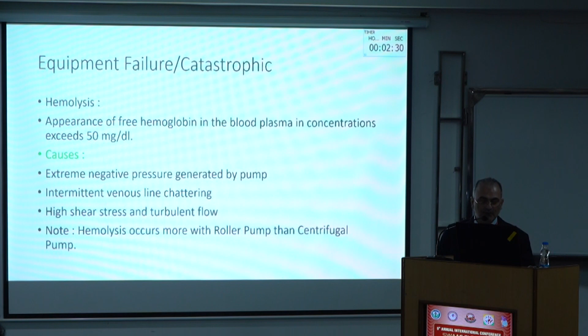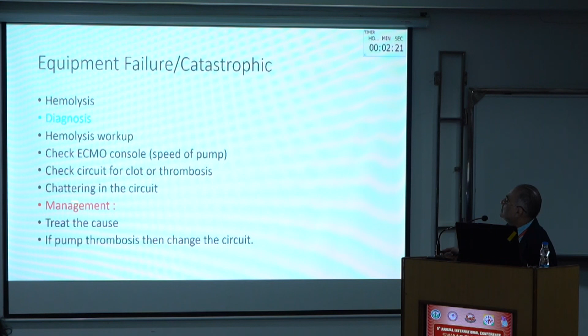And hemolysis in equipment failure is the last one. It appears as free hemoglobin in the blood plasma at a concentration exceeding 50 milligrams per deciliter. Excessive negative pressure generated by the pump causes this damage to the hemoglobin. Intermittent venous line chattering, which my colleague showed you in the slide before, and high shear stress are causes, and hemolysis is much more common when you use a roller pump rather than centrifugal pumps for your patients. Diagnosis needs a hemolysis workup: check the ECMO console, the circuit, chattering in the circuit, and you should treat the cause when this happens.